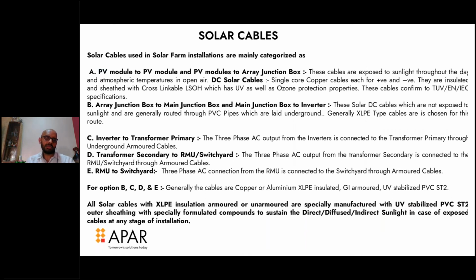Coming to solar cables, basically solar cables in the solar farm are categorized, I would say, into 5 categories. One would be the PV module to PV module and the module to array junction boxes. These cables are generally exposed to sunlight through the day and the atmospheric temperature as well. So there we advise using DC solar cables, because the single core cables are for positive as well as negative. They are insulated with cross-linked zero halogen compound, which is XLPO, which has UV properties as well as ozone protection. And these are manufactured as per TUV EN specs, or even as per the UL specification if required.